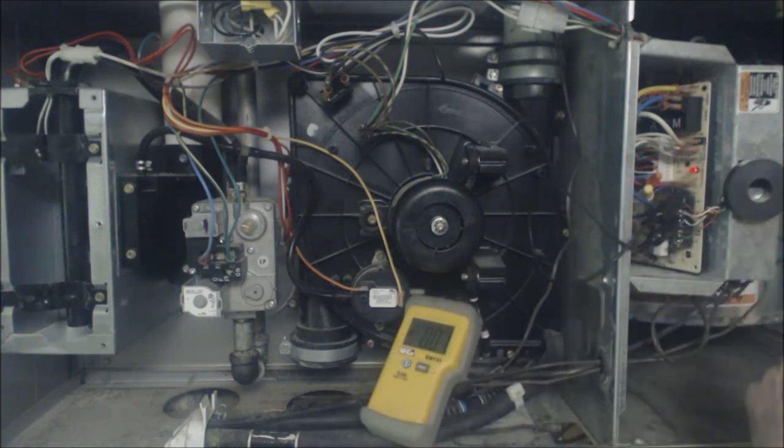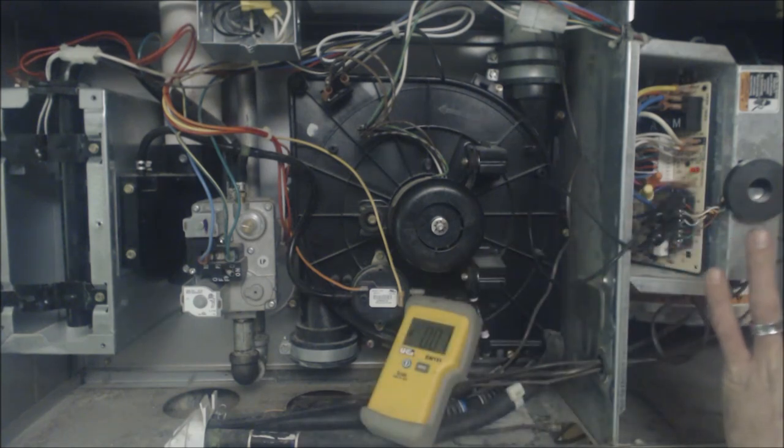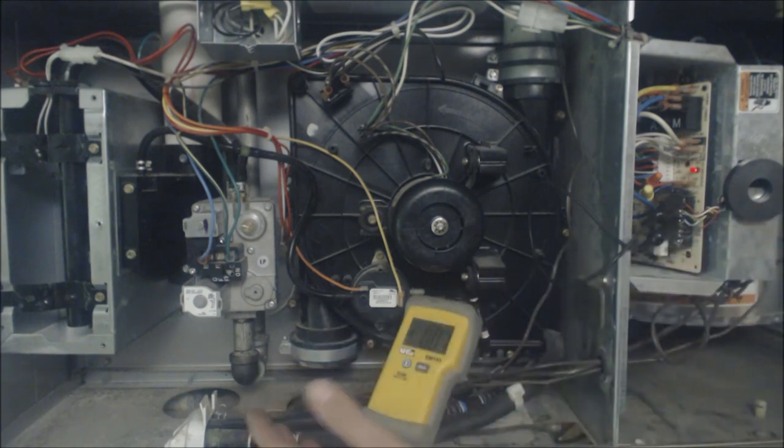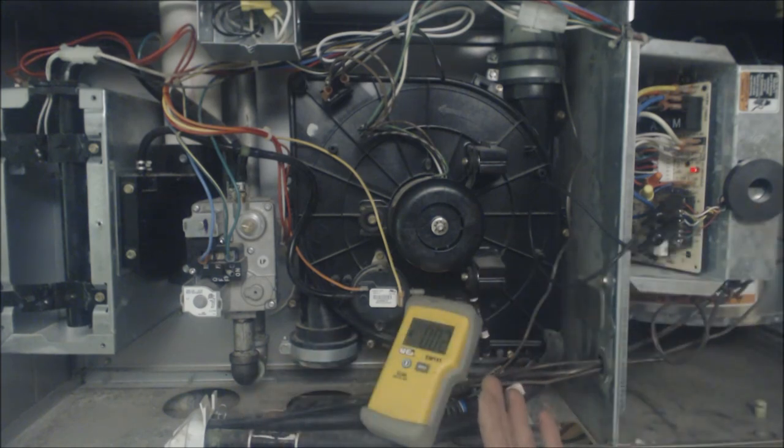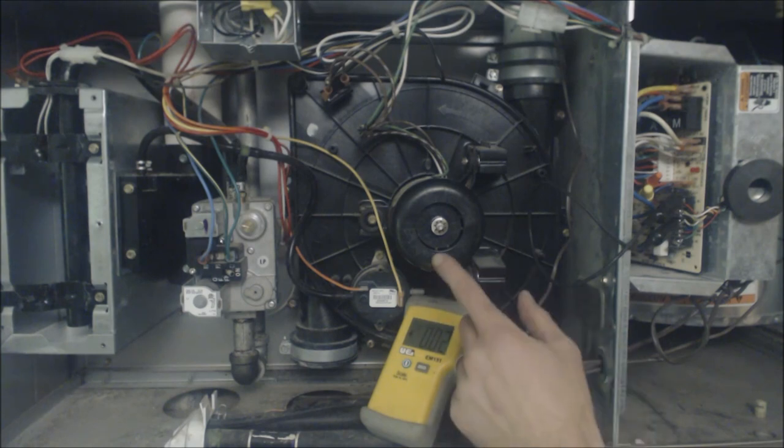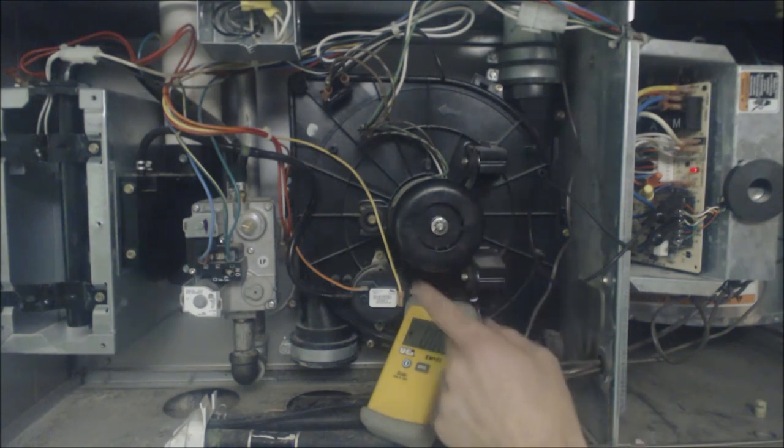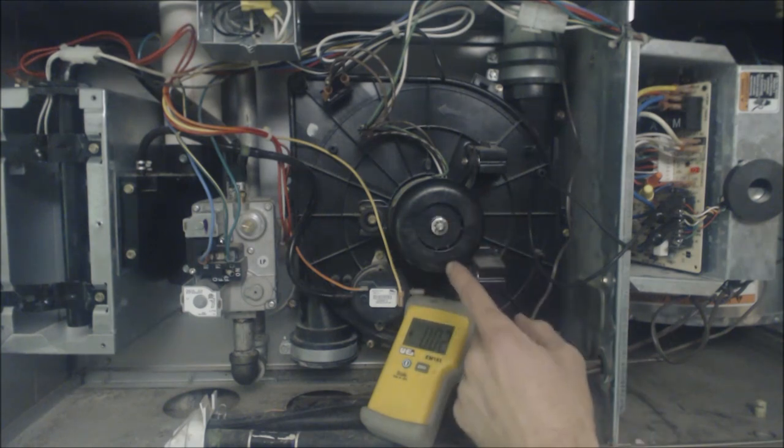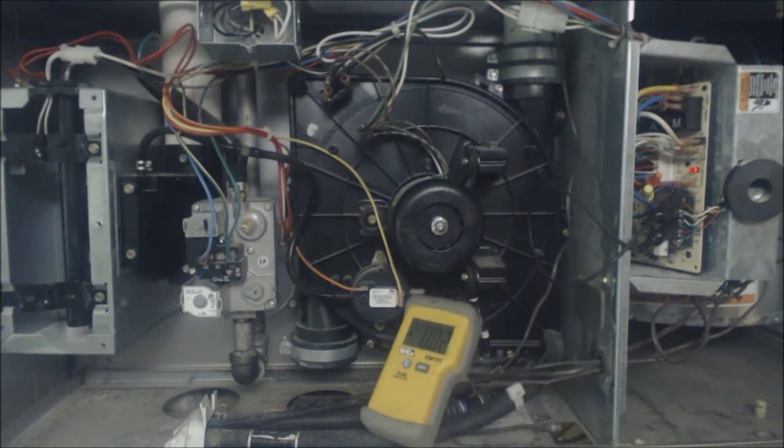Okay, anytime you turn the power off to the furnace when you turn it back on, the blower motor is going to turn on first and then after it cools down the heat exchanger, basically you know usually around 30 seconds or so, then the sequence of operation will start with the inducer motor.